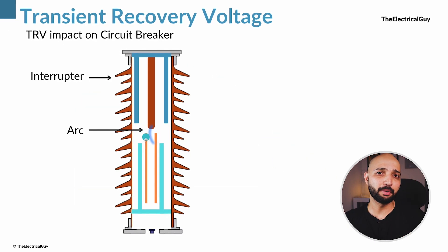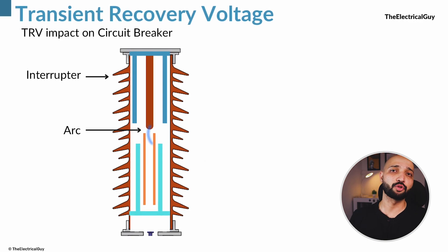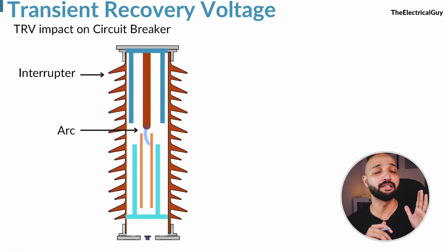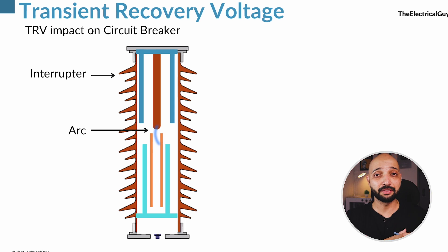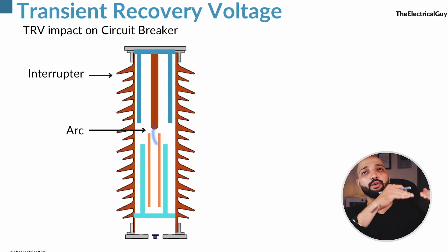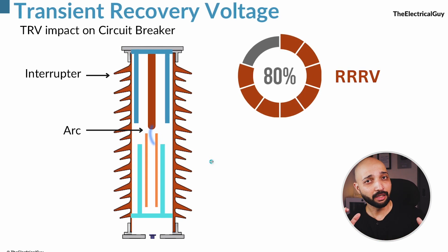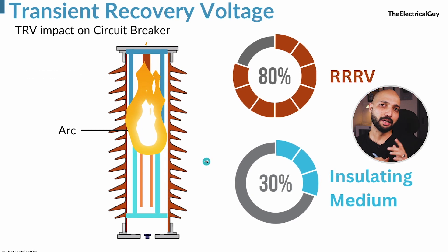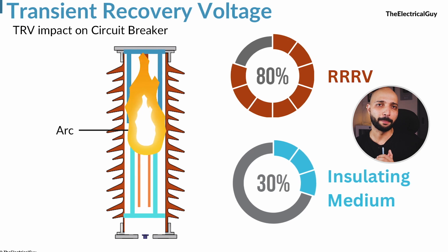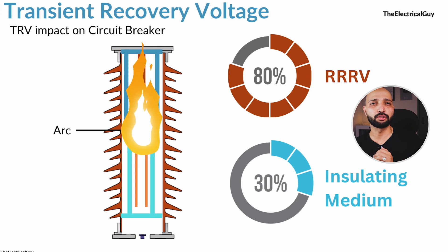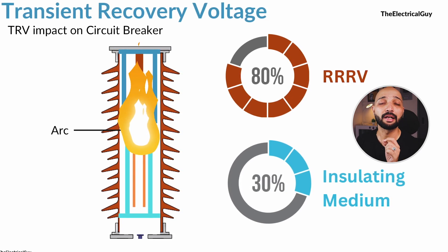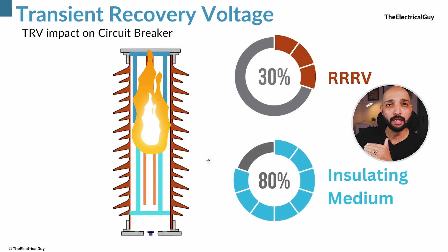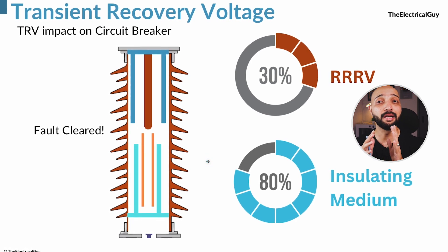When the circuit breaker is interrupting a fault, it results in arcing in the interrupting medium. During the process of interruption, the arcing medium is trying to regain its insulating properties. For the interruption to be successful, the interrupting medium must withstand this fast rising recovery voltage. There is essentially a race between the interrupting medium transitioning from a conducting state to an insulating state against the rising TRV. If the rate of rise of recovery voltage — RRRV — is greater than the speed at which the medium regains its insulating strength, the breaker will fail to clear the fault and the fault current will continue to flow via the arc.